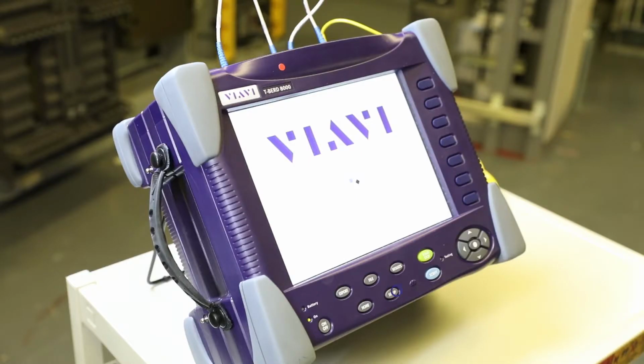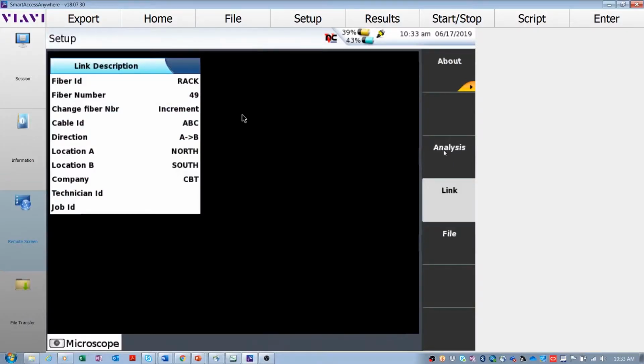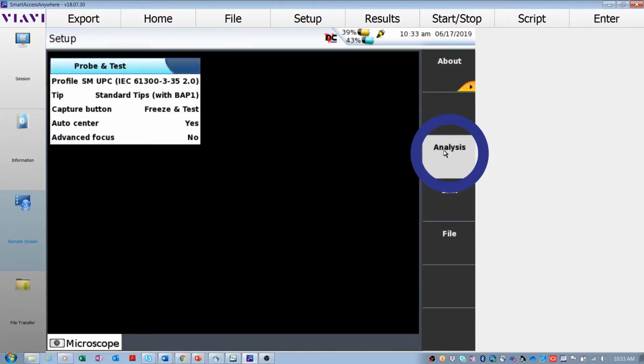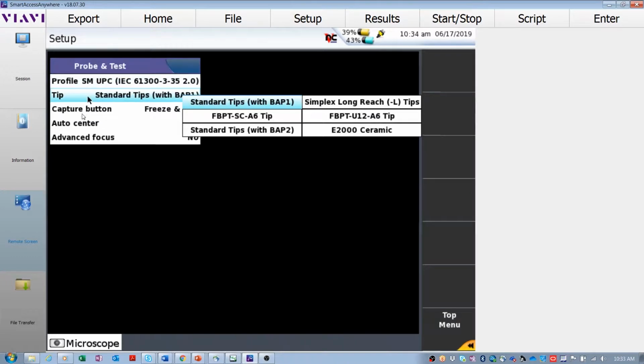Press the Setup hard key. Press the Analysis soft key. Select the correct tip and profile, commonly single mode UPC and standard tips. Most users set Capture button to freeze and test and Auto Center to yes.